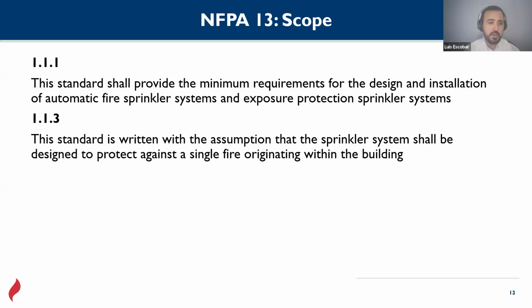NFPA 13, this standard shall provide the minimum requirements for the design and installation of automatic fire sprinkler systems and exposure protection sprinklers. As we saw in the previous slide, how? The keyword is how. How do we need to do this? How do we install? How do we locate? How do we slope the pipe, for example? And very important, this standard is written with the assumption that the sprinkler system shall be designed to protect against a single fire originating within the building.